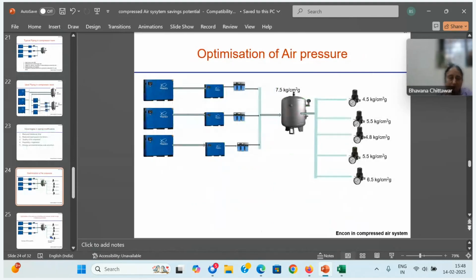Optimizing air pressure is not as easy as everybody thinks. Most consultants or energy auditors will simply ask them to reduce the pressure. Never make that mistake. First, study the end user application. Reduce the pressure at the compressor room by 0.1 kg only, not more than that. Check at the user end what the pressure is. If pressure reduces, you increase the set point at the regulator. These are all proportional. If the air pressure at the compressor is 7 and you set the regulator at 4.5, if you reduce it to 6.5, it will be 4 here. So while you reduce there, you have to increase the setting here. Then only can you achieve the result.